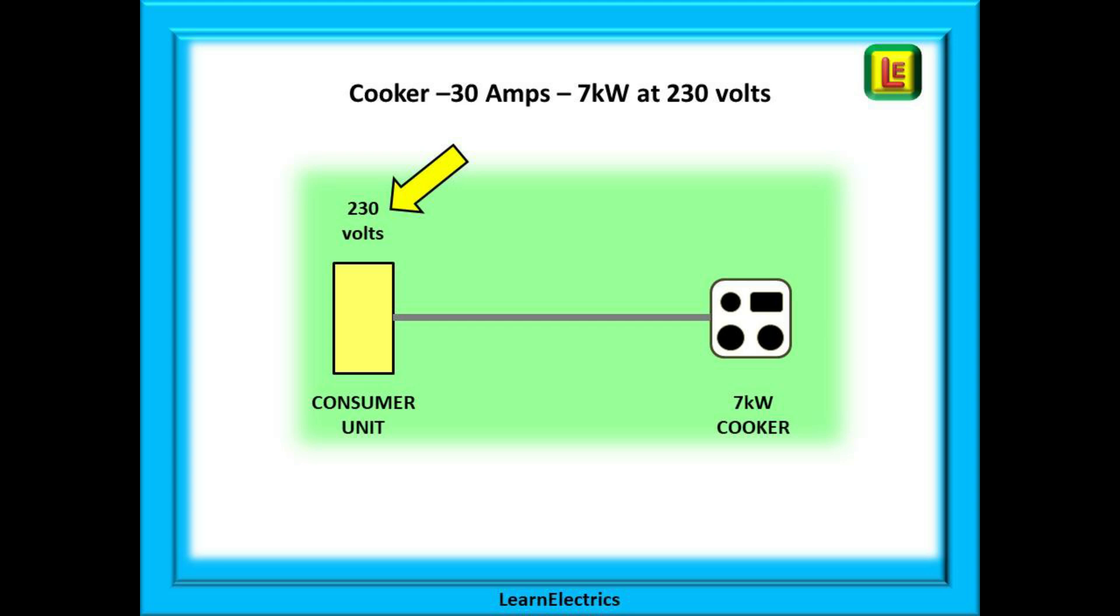A 230 volt seven kilowatt cooker will consume 30 amps of current at full load. But when fully loaded, when everything is turned on maybe at Christmas or for Sunday lunch, the voltage appearing at the cooker may only be 220 volts. This means that 10 volts has been lost in the cable. The 30 amps of current flowing along the cable means that up to 300 watts of power will be lost in the cable. First, 300 watts of power is going to warm the cable up, and secondly, someone has to pay for that 300 watts. It's not getting to the cooker, so it's lost energy to the customer, thrown away money.